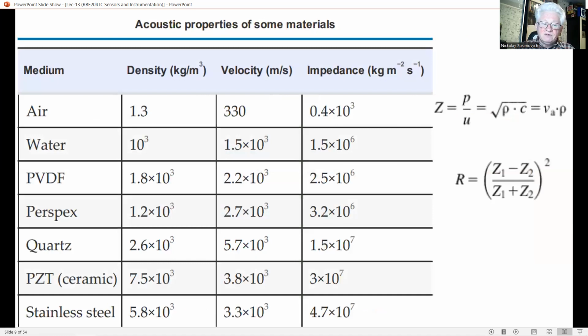PVDF has a relatively low acoustic impedance, as you can see in this table, making it an attractive material for ultrasound applications. The flexibility of the material allows operating in bending mode, whereas the ceramic sensors usually operate in thickness mode. Other piezoelectric materials have been studied for their suitability as acoustic transducers, for example porous film with artificial electric dipoles.